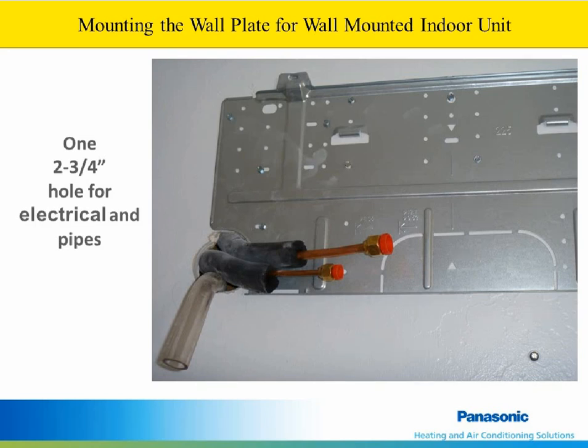Anchors and screws for the wall plate are supplied, but you can also use your own if needed. A 2 3/4 inch wall penetration is all that is needed to route the lines. If the wall plate is installed on an uneven wall, it could cause the unit to vibrate or become noisy. Be careful not to pinch the drain line and continue the slope or pitch so there's proper condensation drainage. There should also be no traps in the condensate drain lines.